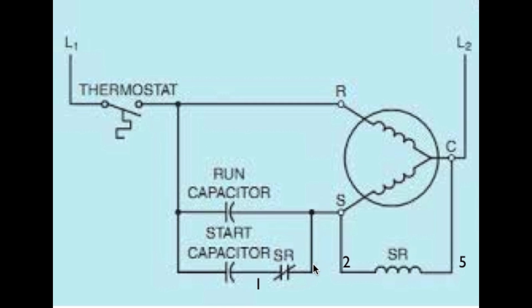Normally when this thing is not running, power is available through the normally closed relay to the start to give this the boost. And as that back EMF rises and energizes the relay, then this opens. So that's the one terminal that's going to go right to the start cap.